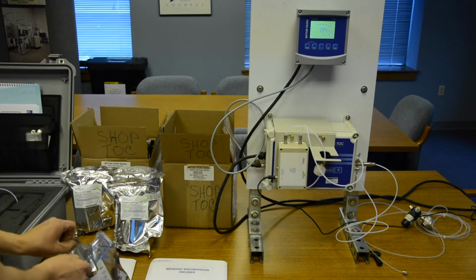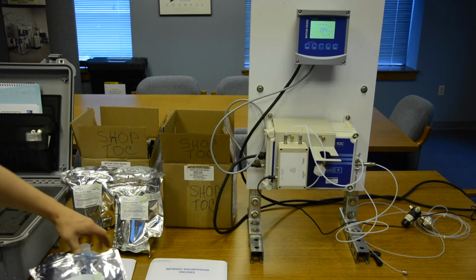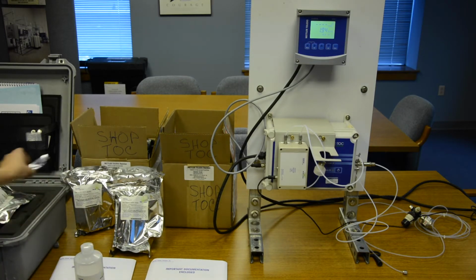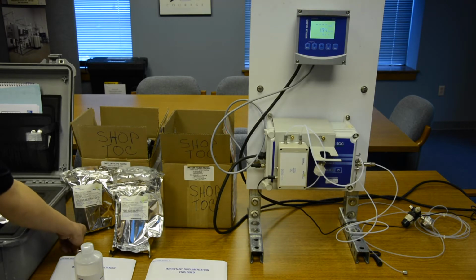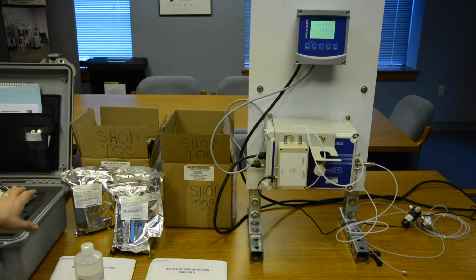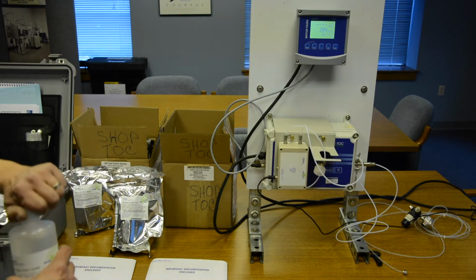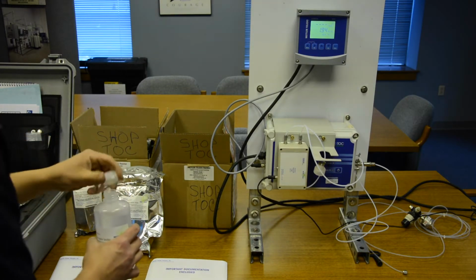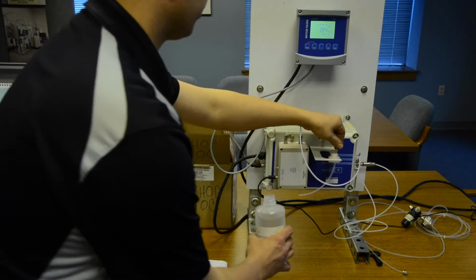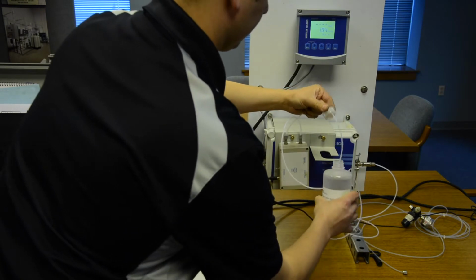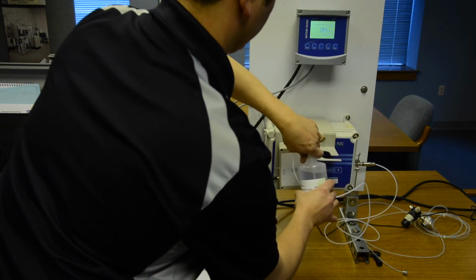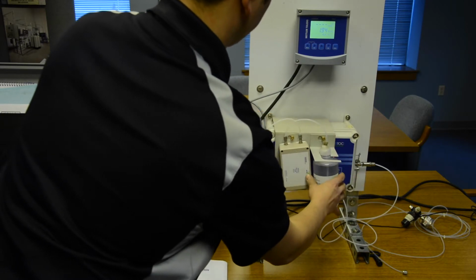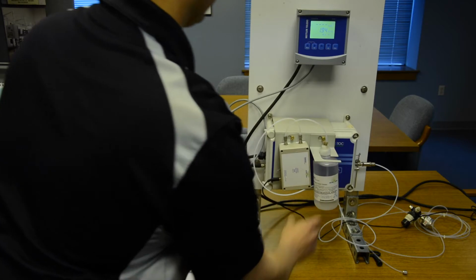This is the first solution that we want to test and also the one that we're going to use for calibration. I also recommend that you use the blank water solutions if you have a feeling that the pump may not be working properly, or if you're trying to make sure that the unit has proper flow. Use the blank water first so that you don't use up the calibration solution, because once you use it up, you no longer have any and you've just ruined a calibration. So start off with the 500 part per billion solution. This is 503. We're going to open that up and place that on our TOC unit. Once it's been placed on the unit, turn on your injection pump and let it begin to flow through the unit.